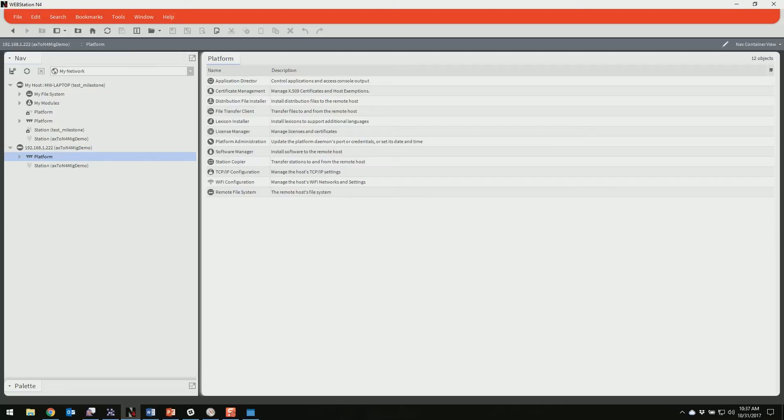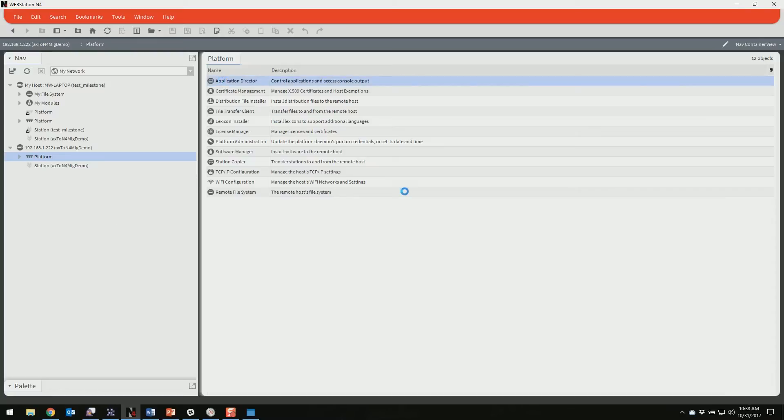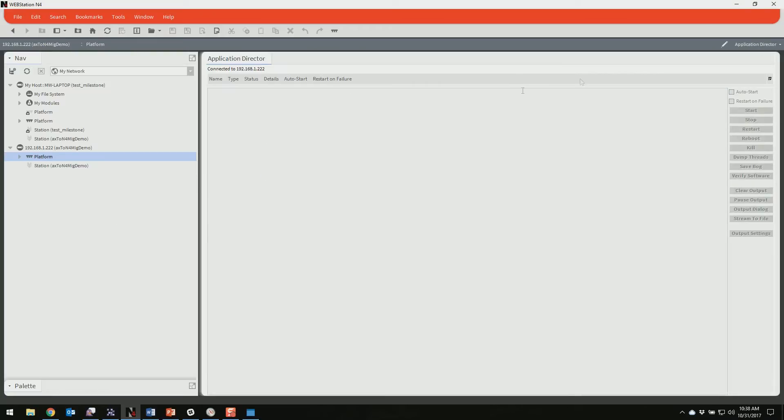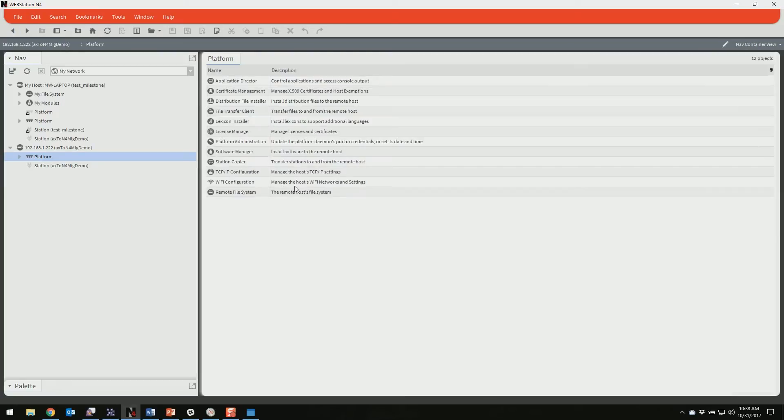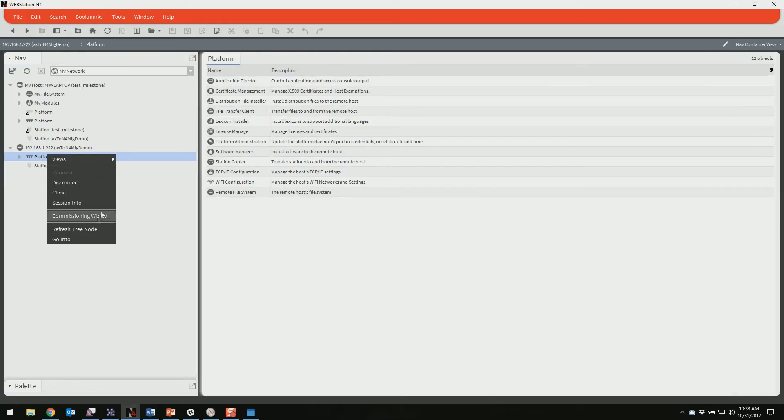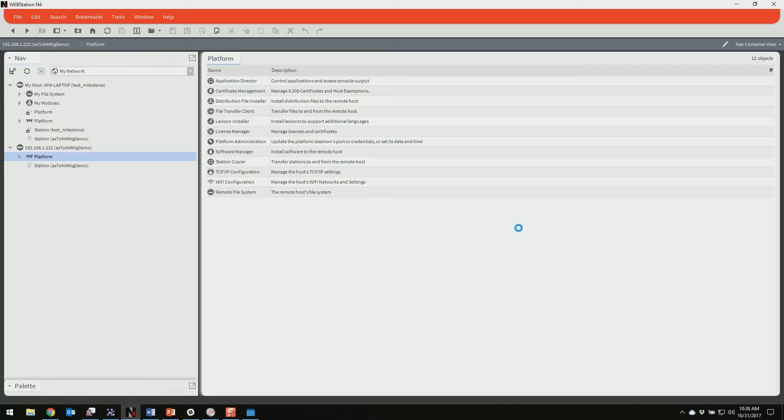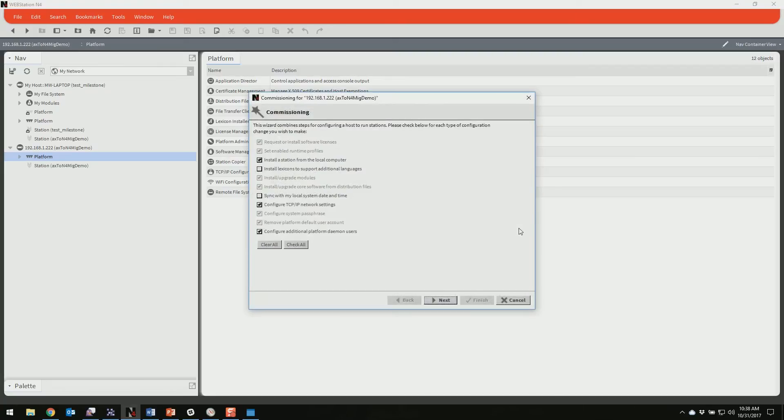Again, take a look at the documentation that's accompanying this video. We've got a list of all the default credentials for all the different types of Jaces for the platform. So we're logged into the platform here. We can see it's empty, there's no station in it. So what we need to do is right click on our platform and start up a commission.